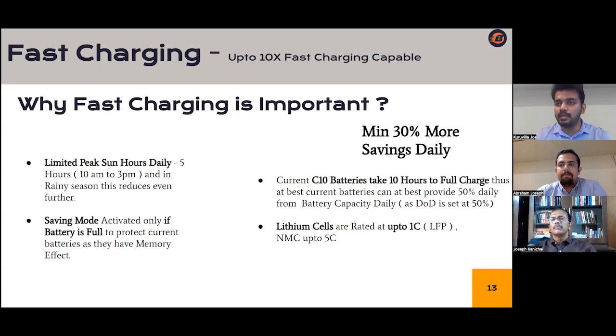Now, in case of lithium batteries, a fun fact is that you can actually charge the lithium battery within just 1 hour. We don't recommend it because it can degrade the battery, but it is possible. So we recommend a charging rate of around 0.3 C, up to 0.3 C, which is actually 3 times faster compared to a lead acid battery. Now, this fast charging has two advantages: you can charge the battery faster—that is one obvious advantage—and you can also drain more from the battery as well.